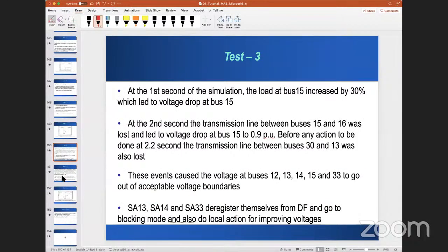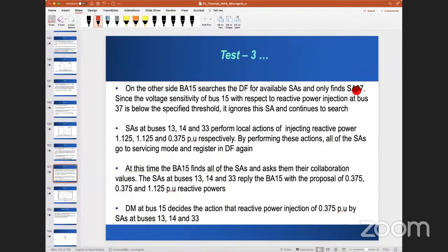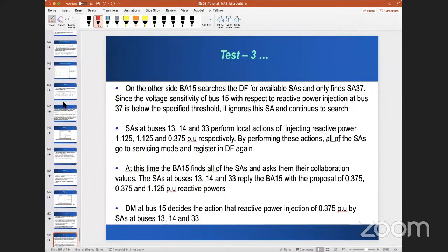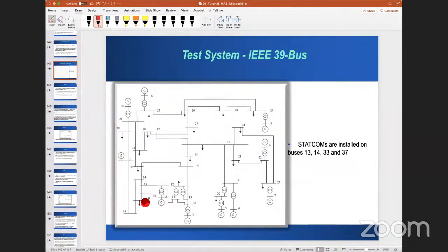All the registers, okay, and then we have only SA37 available. Since the voltage sensitivity of bus 15 with respect to reactive power injection from SA37 is below the specified threshold, it ignores this SA and continues to search. Now, it's very clear: 37 is much far from the influence region of this one, so whatever injection it does will have a very, very small effect. And the violation is severe, 0.9 is much, much far from the lower limit. So even if SA37 is available, it's not going to help this agent, okay?